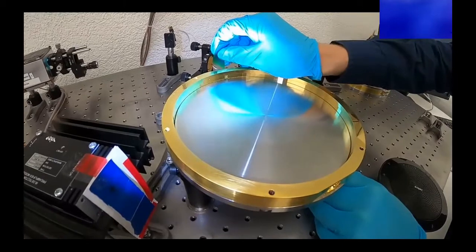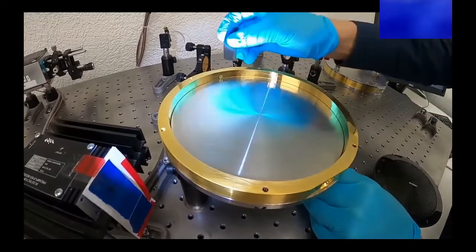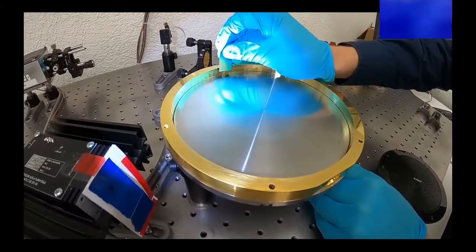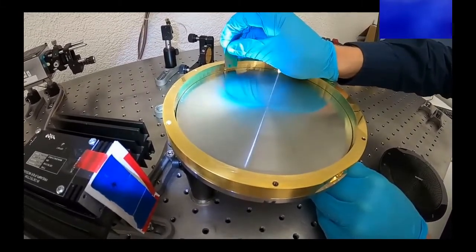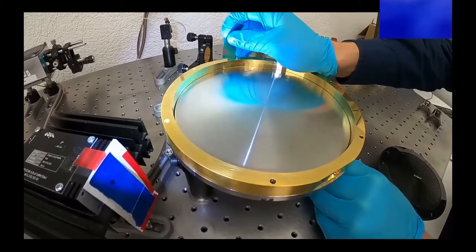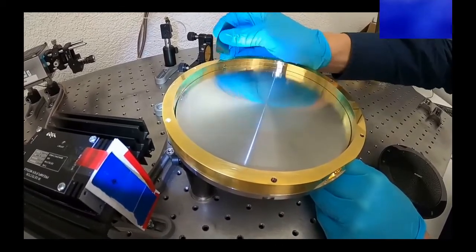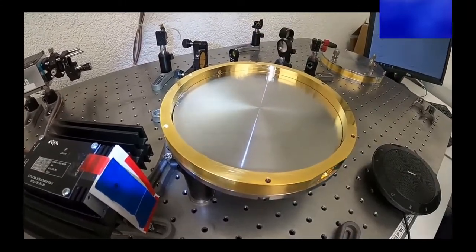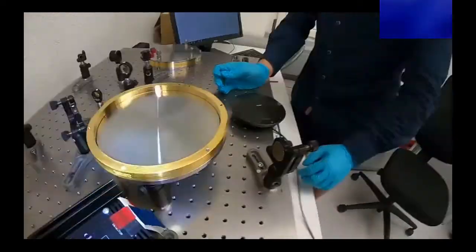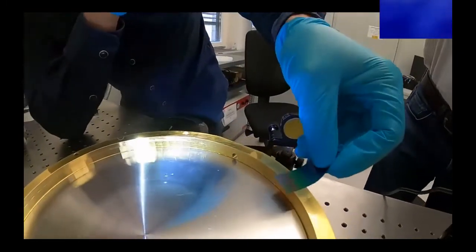So now with the thermal paper we can see the beam, and now I'm just trying to align it so that the beam goes through the middle of the hole, which is already the case. Then the second thing, and that will be all, is to hit the right mirror. So the first mirror has to be a specific mirror, and it is basically always the second mirror from the output aperture.